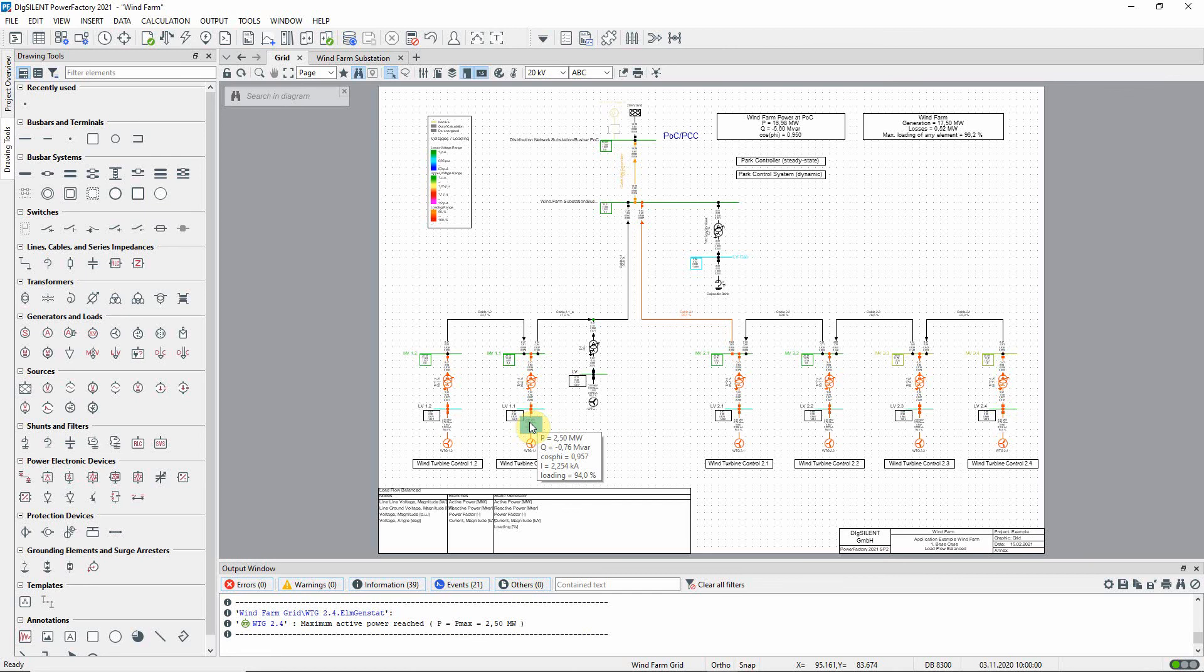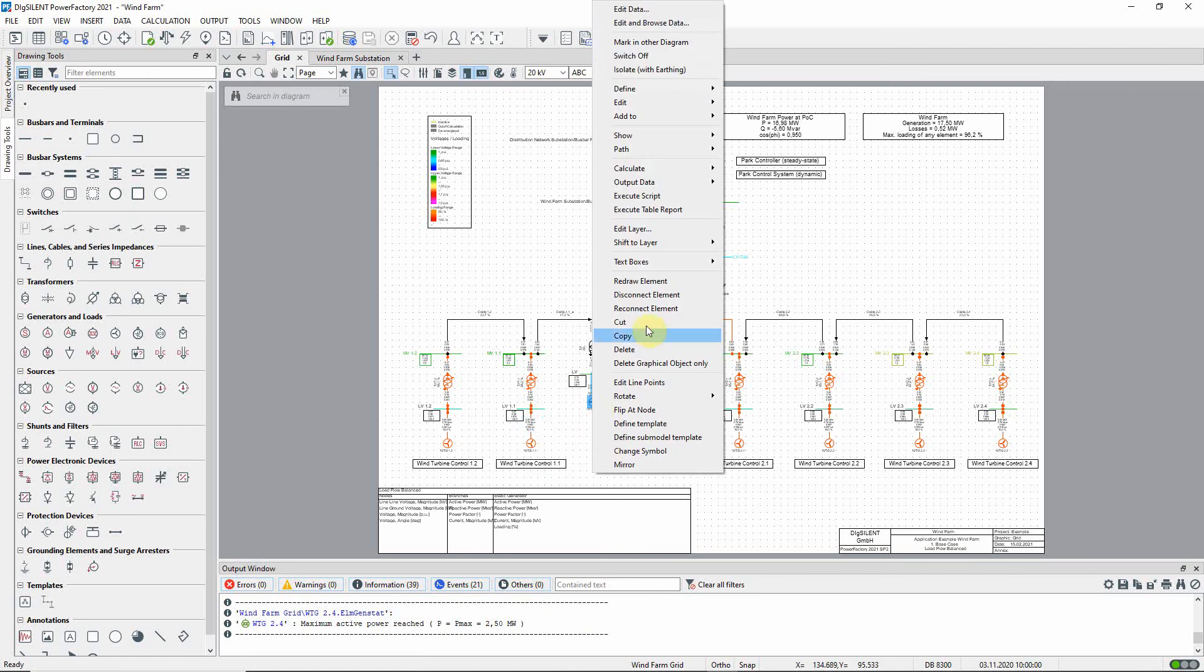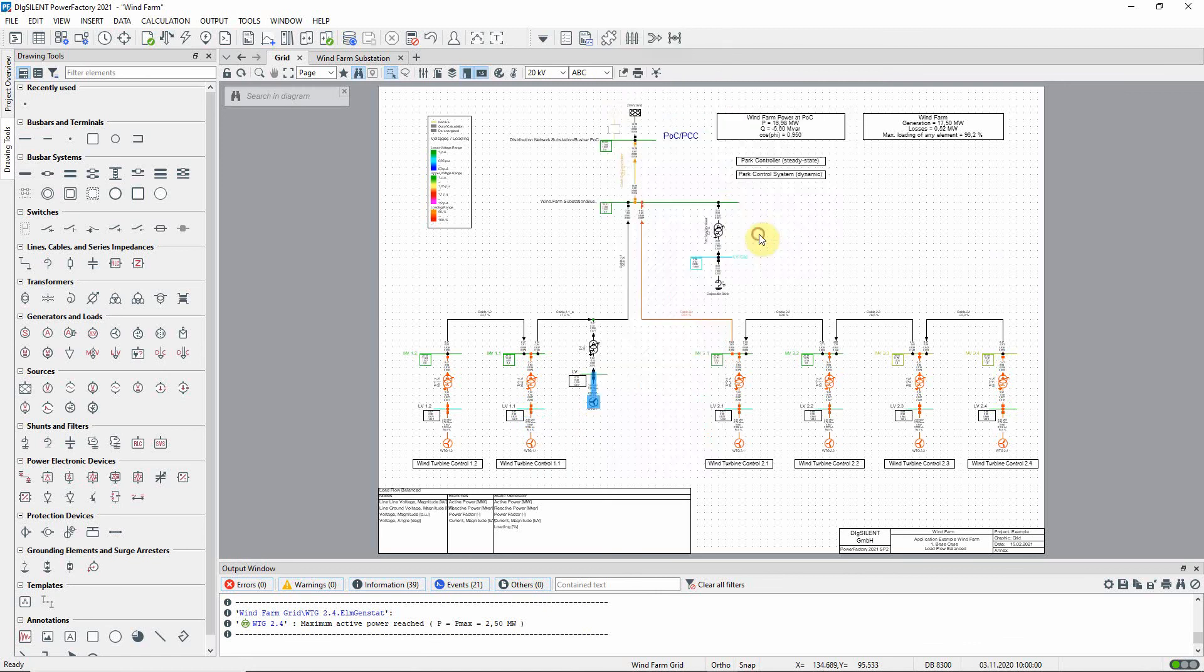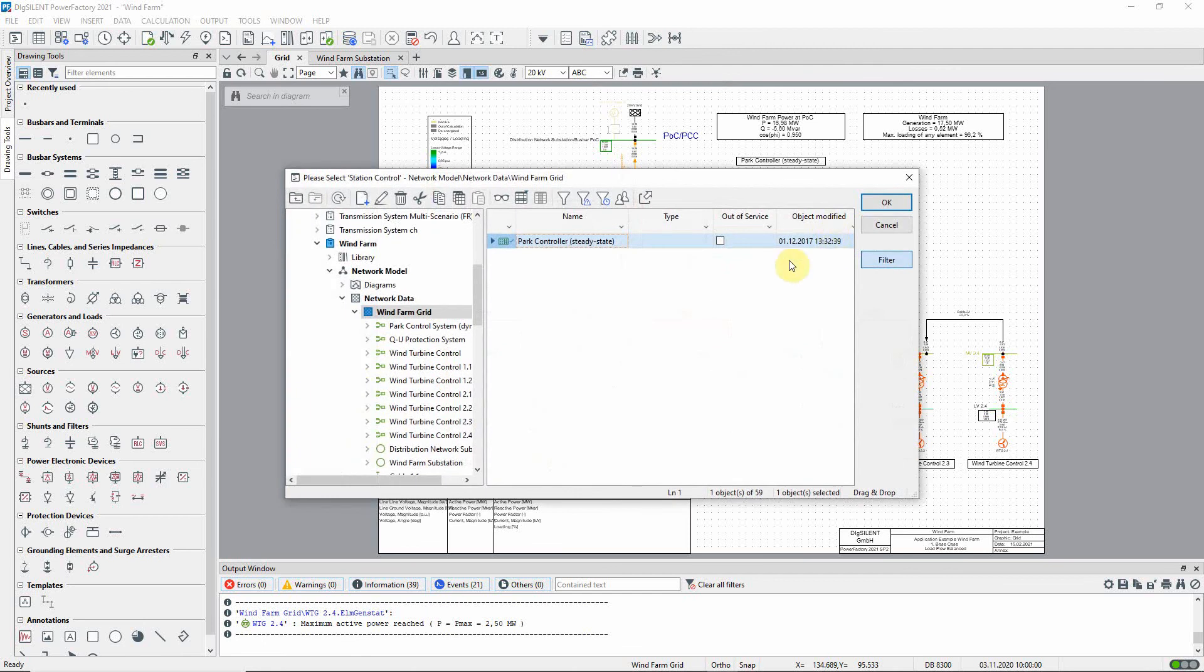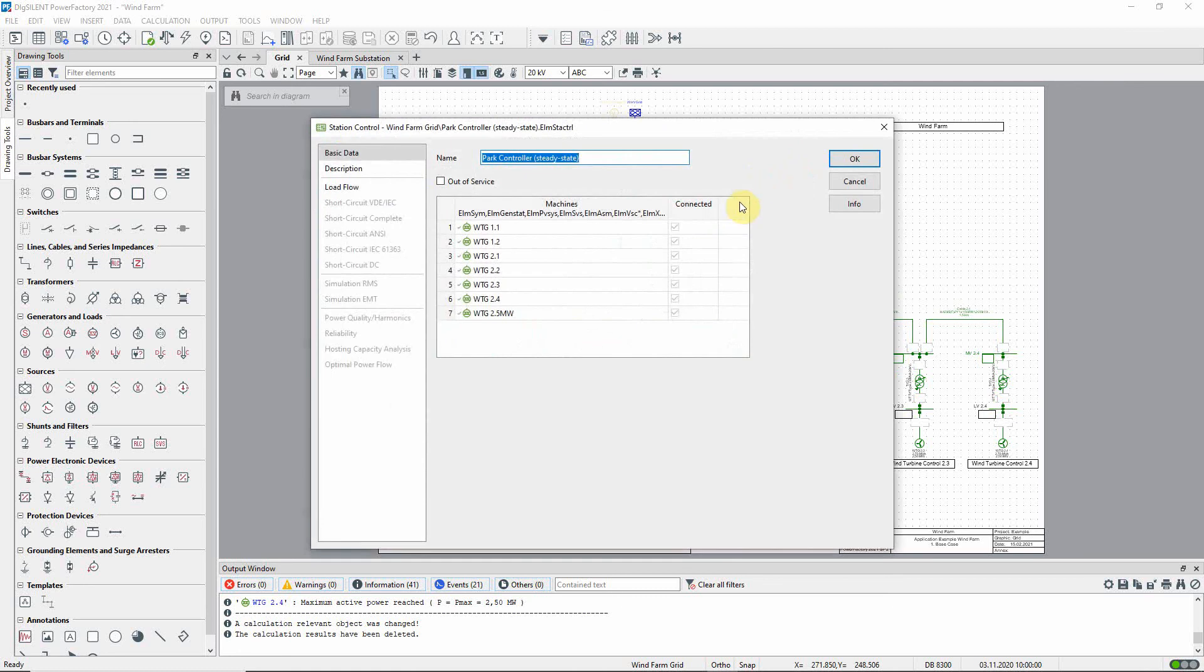This is because the new turbine is still configured to local control. In order to let the new turbine participate in the reactive power control of the wind farm, we need to add it to the station controller. Right click on the new turbine and select add to and then station control. Select the station controller. Take another look at the controller. You can see that the new turbine is at the bottom of the list.